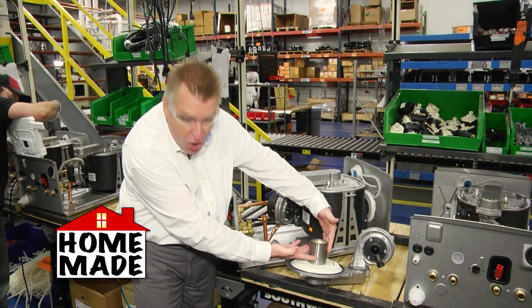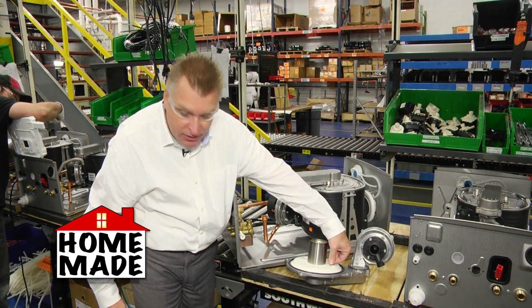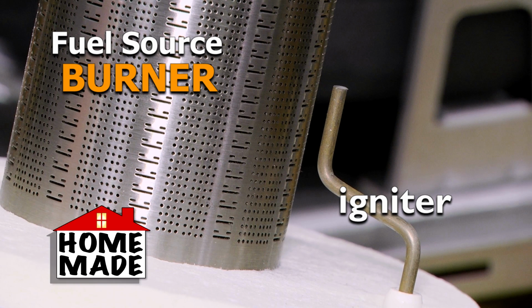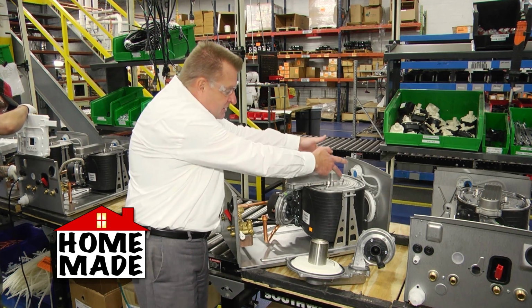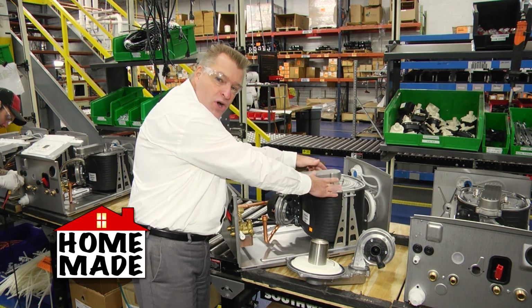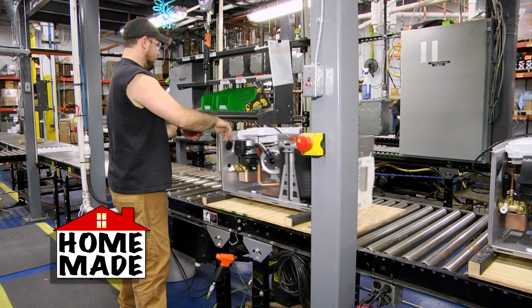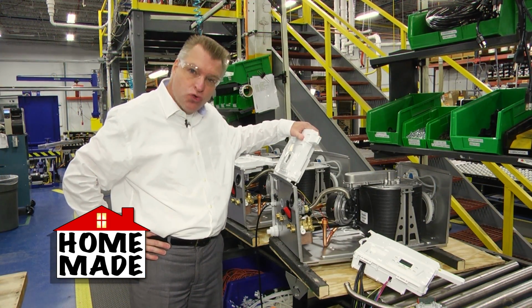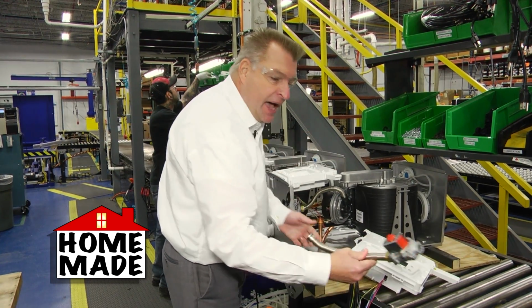The air and gas mixture goes through this thing called a burner. This is an igniter, and basically there's an electric current going through here that produces a spark. This causes the entire flame around this entire burner assembly. That is inside here, which provides the heat source to heat the water that's in those coils. So what takes place at this station here is pretty critical. You have two things here. You have the control and you have the gas valve.